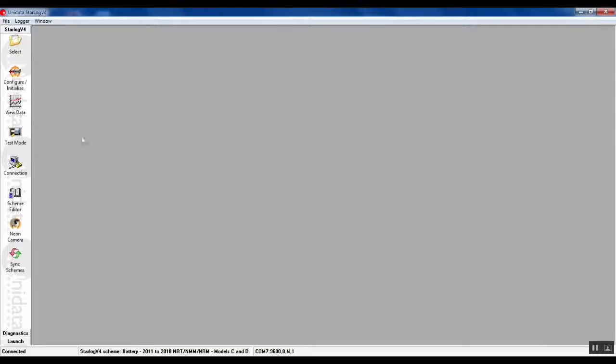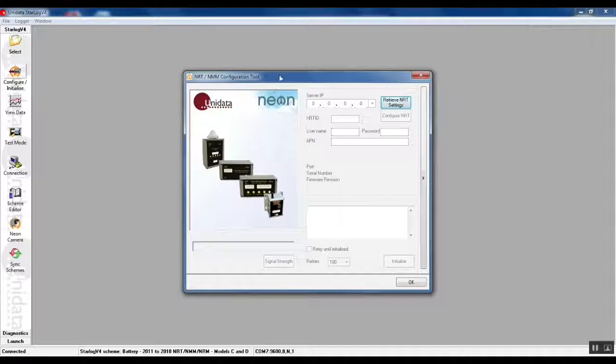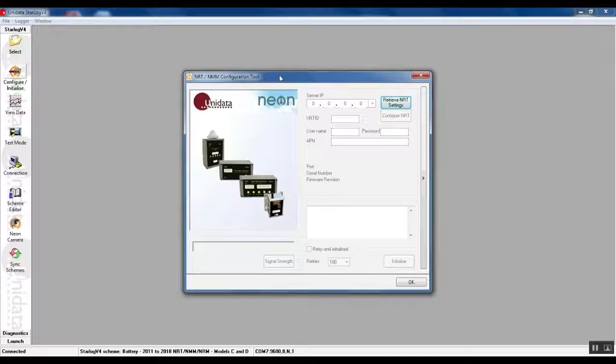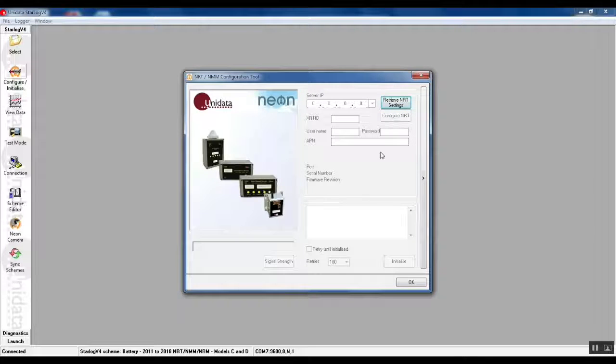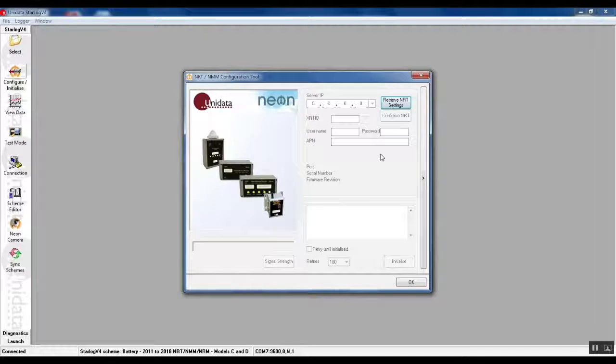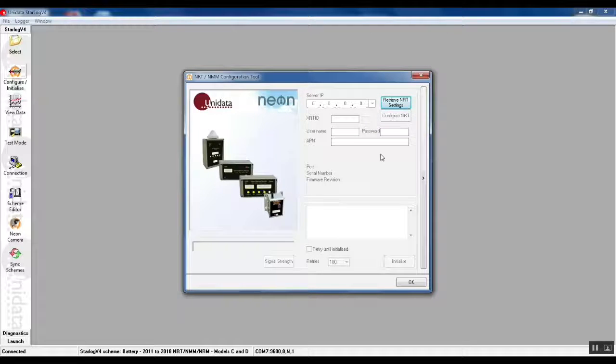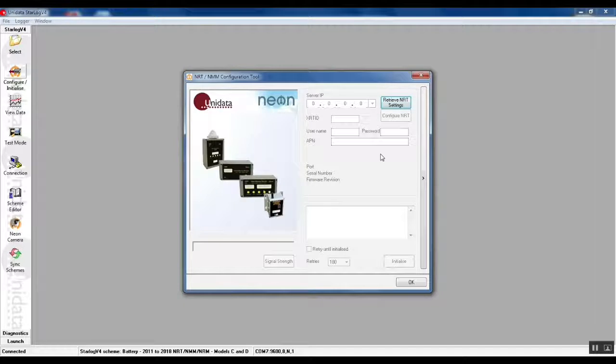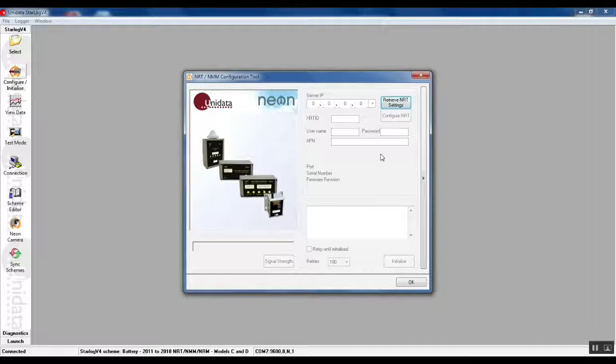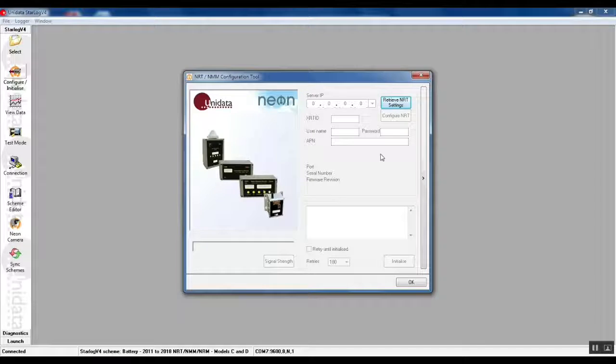Now to configure the NRT we go to the second icon from the top which is configure/initialize. That opens up the NRT configuration tool. This is by far the easiest way to configure an NRT. You have to plug your serial cable into the NRT and make sure your NRT is powered up. The red LED when you first turn on an NRT will light solidly for 10 seconds and then go out.